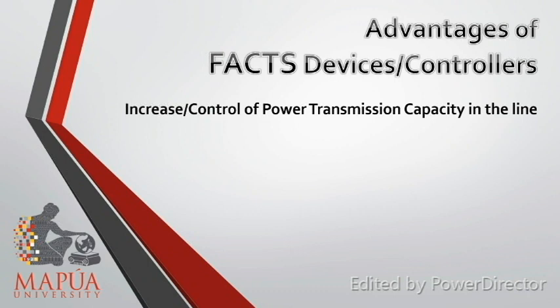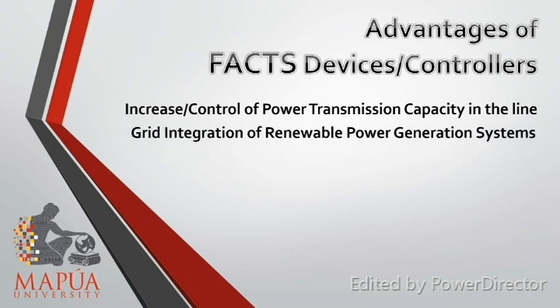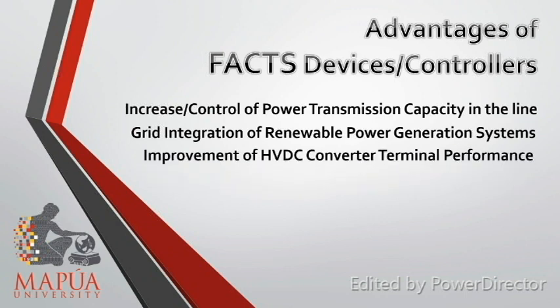Second, FACTS help in grid integration of renewable power generation systems, especially in the case of STATCOM, which has effective control strategies for modulation of real and reactive output power. In addition, it provides greater flexibility in siting new generation. FACTS, specifically SVC, provides dynamic reactive power support, which improves HVDC converter terminal performance and also filters harmonics entering the AC systems.